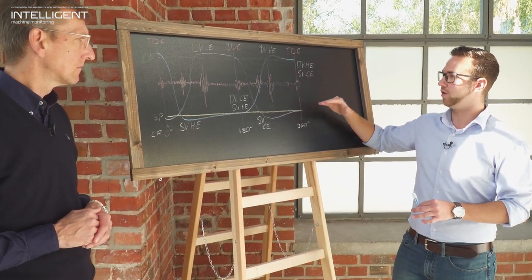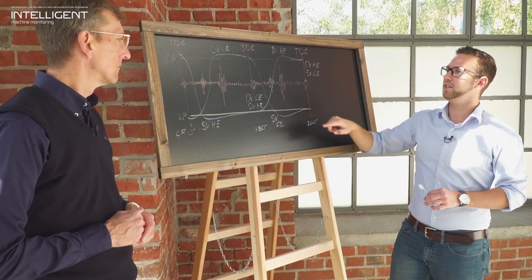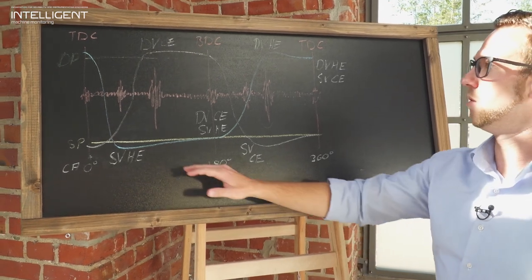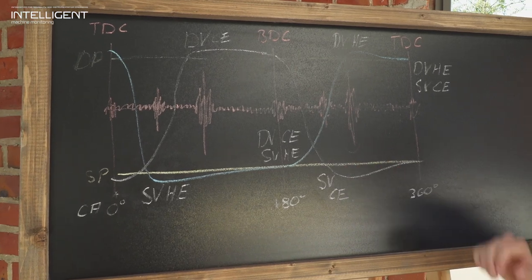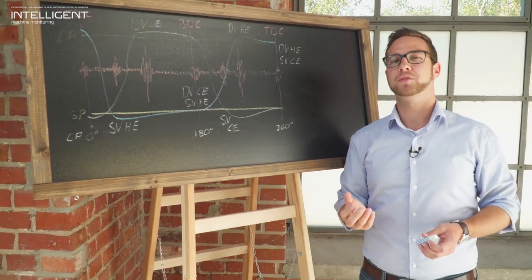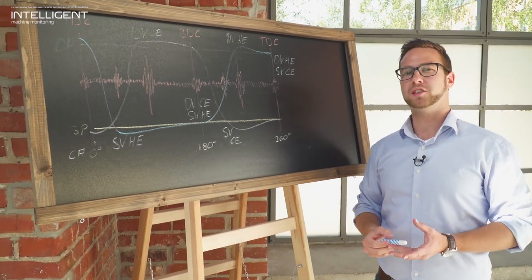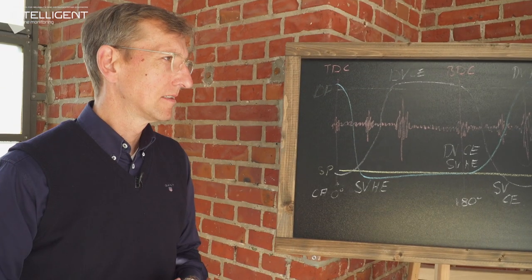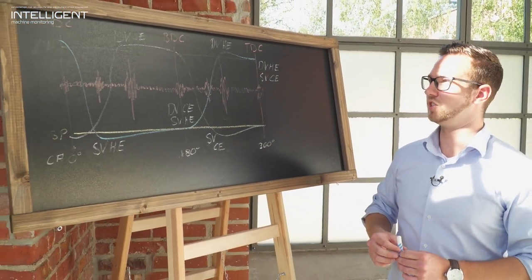We are having the pressure from suction pressure, which is compressed to discharge pressure level. We are seeing the dynamic pressure in both compression chambers. It's a double acting compressor, so we are having the head end pressure in blue and the crank end pressure in white. What we are measuring with cylinder vibration probes are the vibration peaks created by the valve actions. During one revolution, there are usually eight valve actions on a double acting compressor, four on each side of the compression chambers.